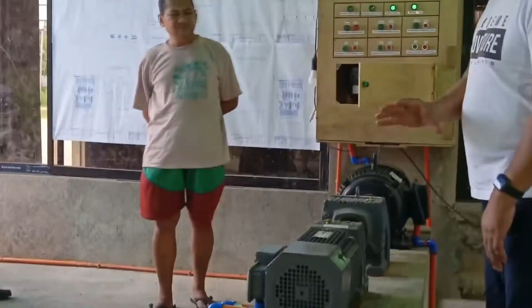So that's why we have already some orders for showcase for the ice plant in Consolation and Mandaue. If you want to work with us, we can. If you need 1,000 kilowatts, I have to double it. I will install 2,000 kilowatts so that one is spare. There must be a spare so that it will run 24/7, 365 days without breakdown. If there's preventive maintenance or a sudden breakdown, the other one can kick in. We have a load sharing and load shedding controller that will automatically kick in.